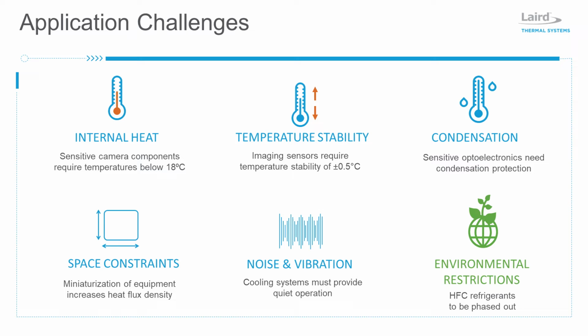Recirculating chillers are used to route heat away from sensitive electronics and efficiently dissipate it into the surrounding environment. Imaging sensors also need to maintain stable temperature control to within plus or minus 0.5 degrees C to assure very high-resolution images are captured. Laboratory technicians continue searching for cooling solutions providing low noise and vibration. While traditional compressor-based systems tend to vibrate and are often noisy, thermoelectric chillers utilize smaller fans and pumps resulting in less noise and vibration.